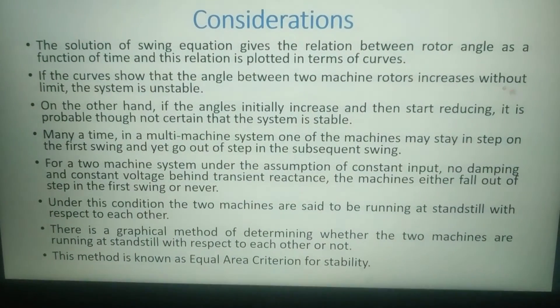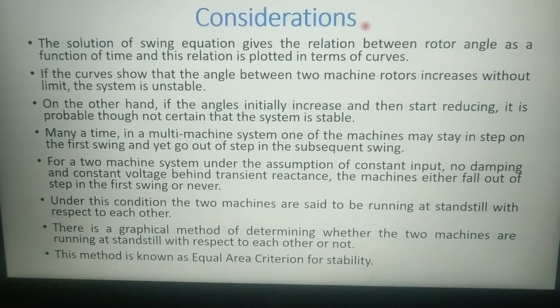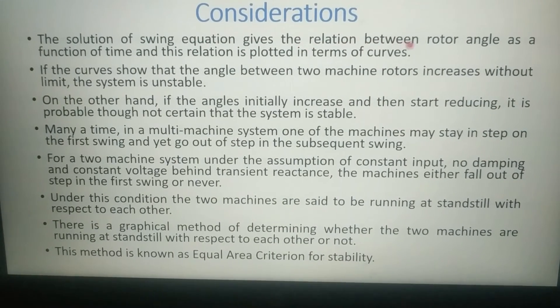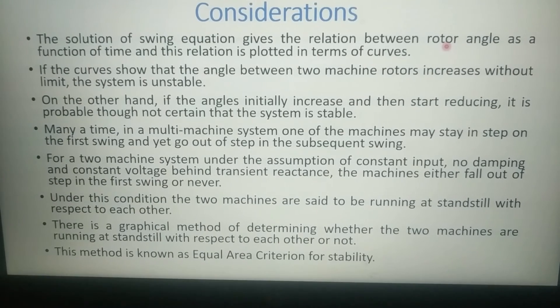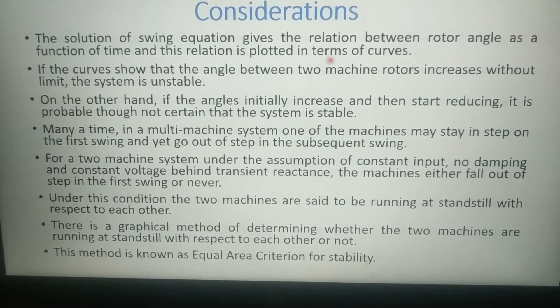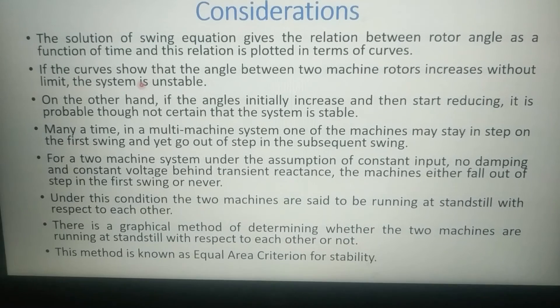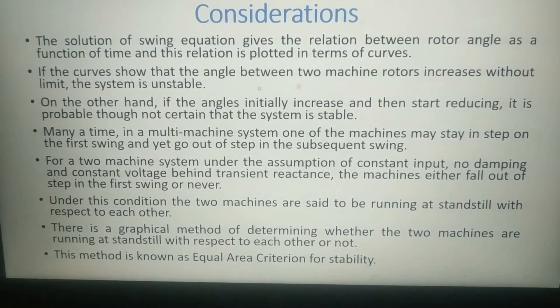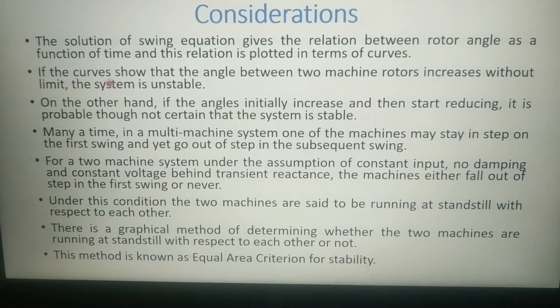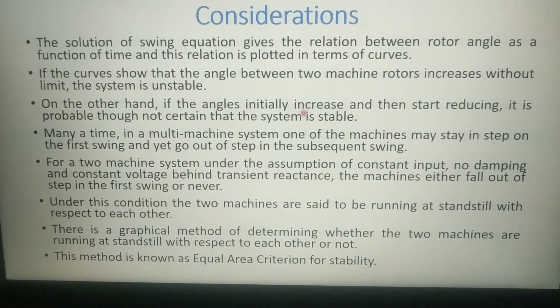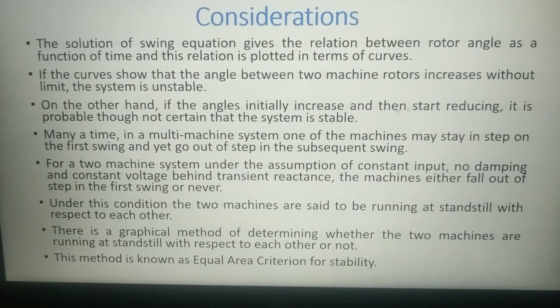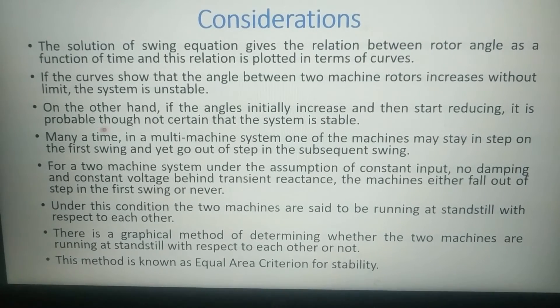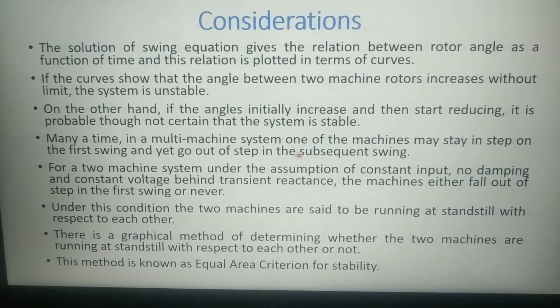From the previous five lectures studied on power system stability, we have some considerations to summarize. The solution of the swing equation gives the relation between rotor angle as a function of time, and this relation is plotted in terms of curves. If the curves show that the angle between two machine rotors increases without limit, the system is said to be unstable. If the angle initially increases and then starts reducing, it is probable though not certain that the system is stable.